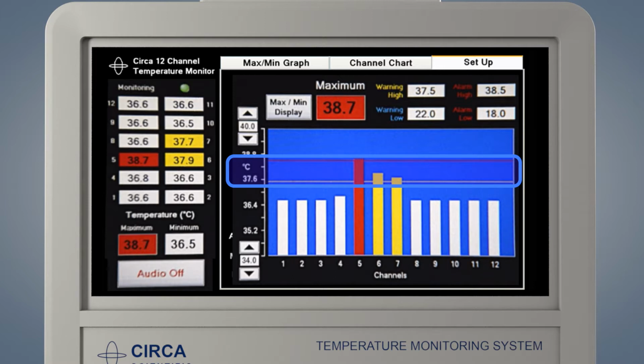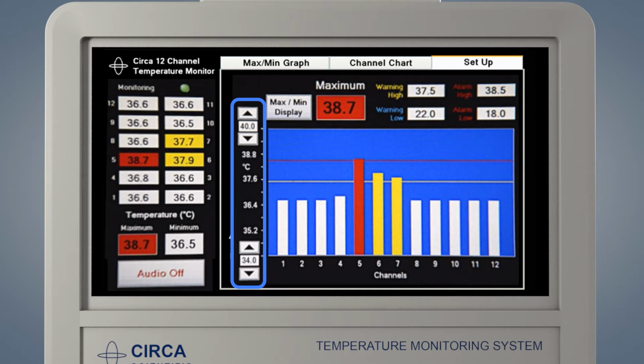The channel chart graph also displays the current warning and alarm settings by yellow, blue, or red lines on the graph. The sensor temperature display and the corresponding bars change colors as temperatures reach warning and alarm limits. The scale of the graph may be adjusted using the up or down arrows on the y-axis of the graph. The individual temperatures are displayed numerically along the left side of the screen. The maximum or the minimum is displayed in the large box above the graph. This box will display the hottest or the coldest temperature.